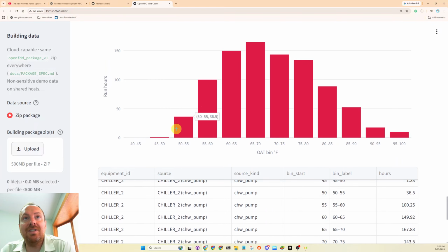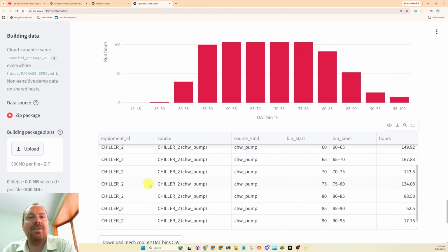I think we saw in the previous videos that the charts were almost 5 degrees off at times. So this is made from the data from the web, web weather made this. What could cause this is that the local outside air temp sensor, which enables mechanical cooling to run if the outside air temperature is above 55, if it's off by 5 degrees, it's causing it to run too soon, when in theory you shouldn't need it.